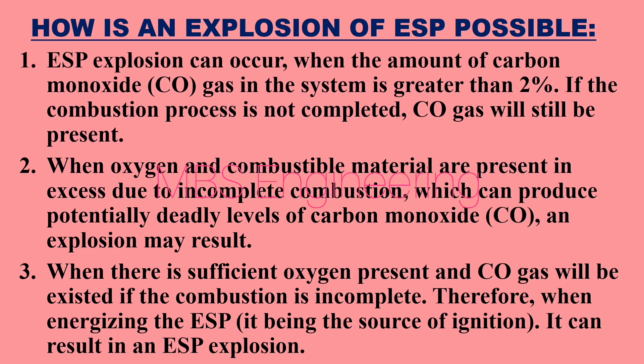Next, we will look at how an ESP explosion happens. Point 1: ESP explosions can occur when the amount of CO gas in the system is greater than 2%. If the combustion process is not completed, CO gas will still be present. Point 2: When oxygen and combustible material are present in excess due to incomplete combustion, potentially deadly levels of CO can lead to an explosion. Point 3: When there is sufficient oxygen and CO gas exists from incomplete combustion, energizing the ESP — being the source of ignition — can result in an explosion.